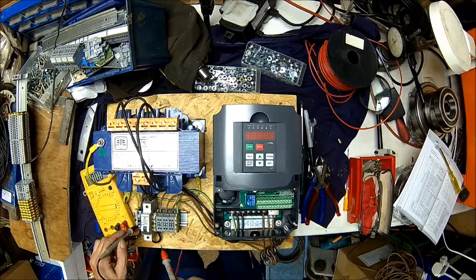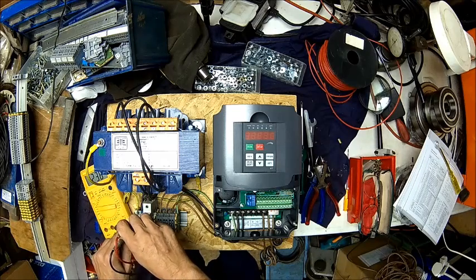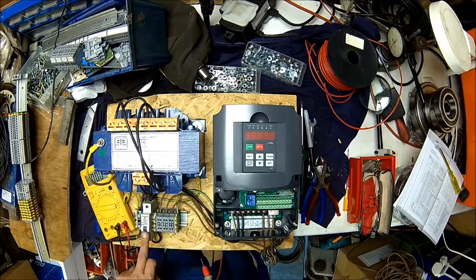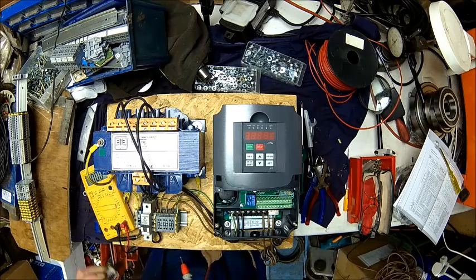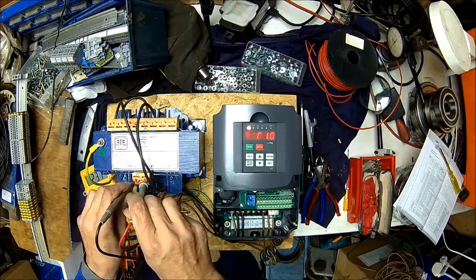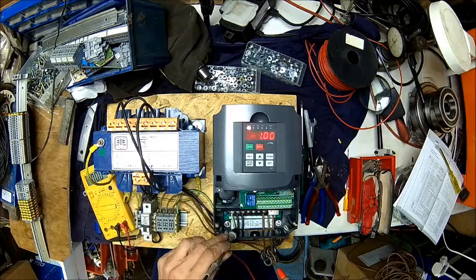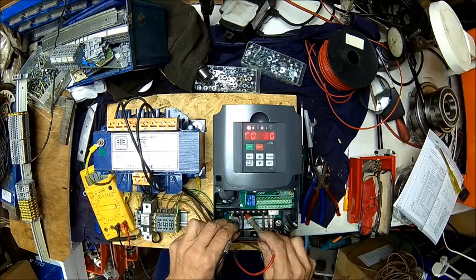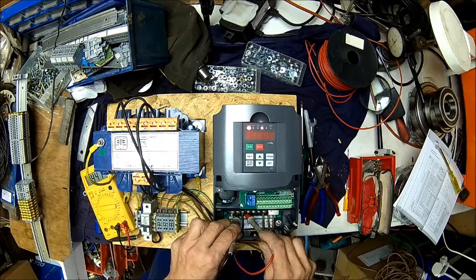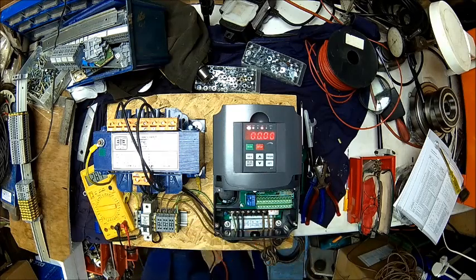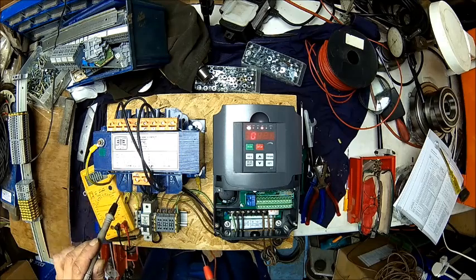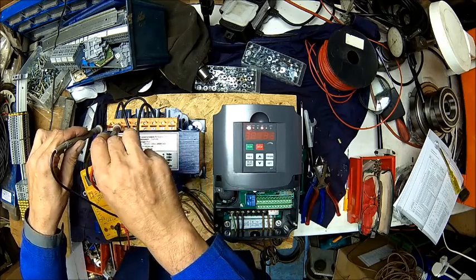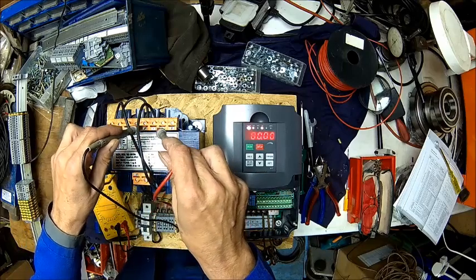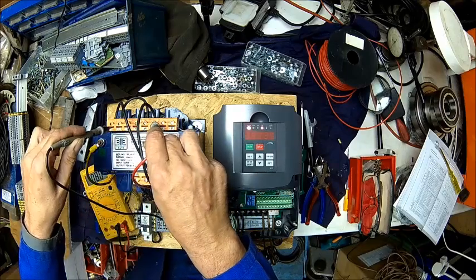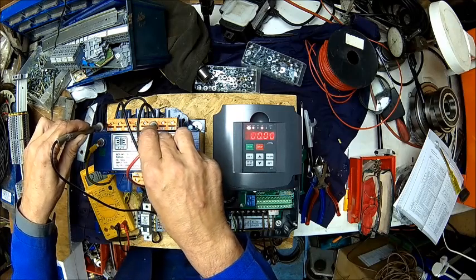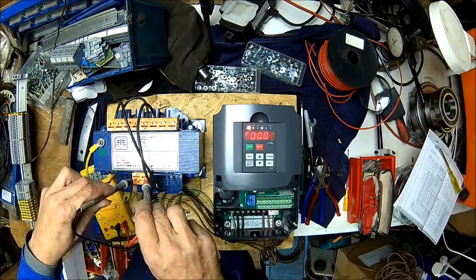Okay, we got mains voltage here on my terminals, 238 volts. We power the thing up. We got 237 here, and we got 440 something here on our inverter. So the phasing of the coils is correct.